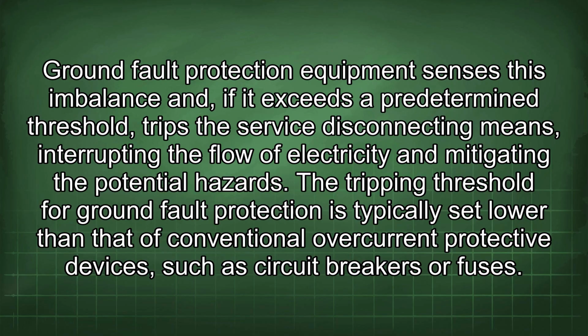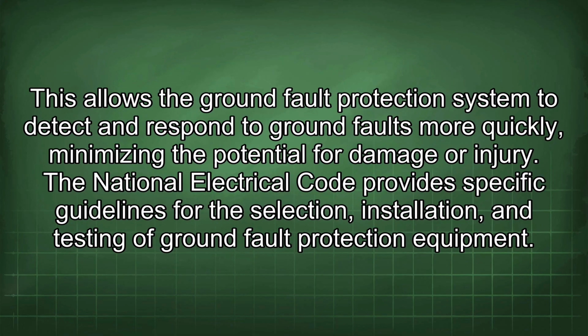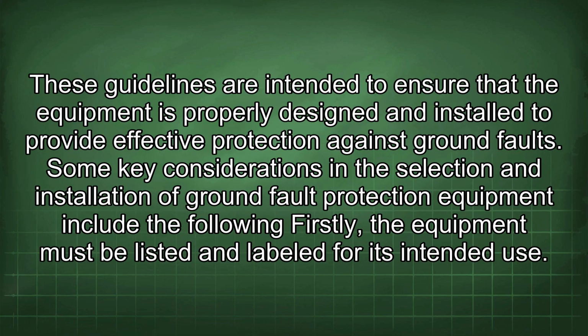The tripping threshold for ground fault protection is typically set lower than that of conventional overcurrent protective devices, such as circuit breakers or fuses. This allows the ground fault protection system to detect and respond to ground faults more quickly, minimizing the potential for damage or injury. The National Electrical Code provides specific guidelines for the selection, installation, and testing of ground fault protection equipment. These guidelines are intended to ensure that the equipment is properly designed and installed to provide effective protection against ground faults. Some key considerations in the selection and installation of ground fault protection equipment include the following.